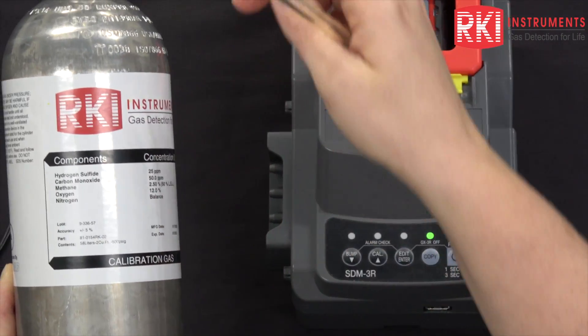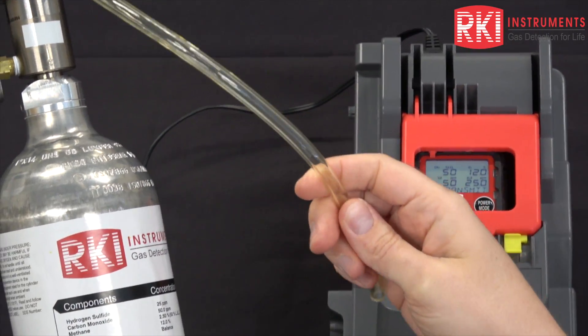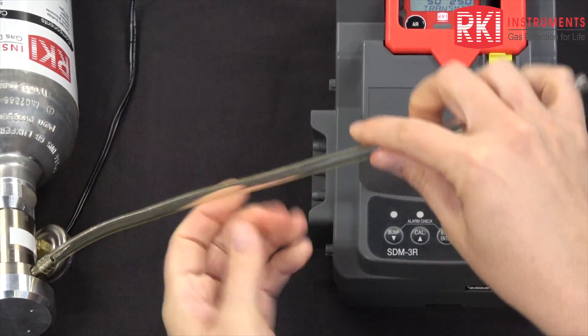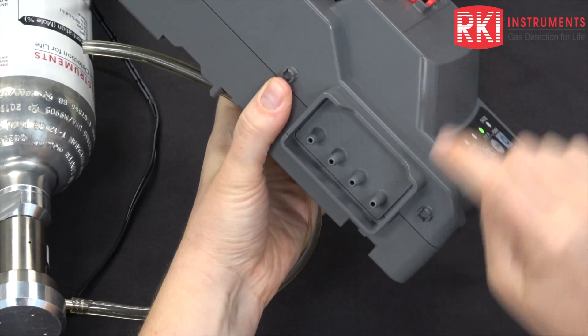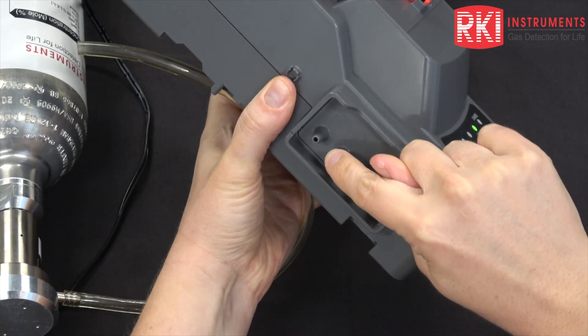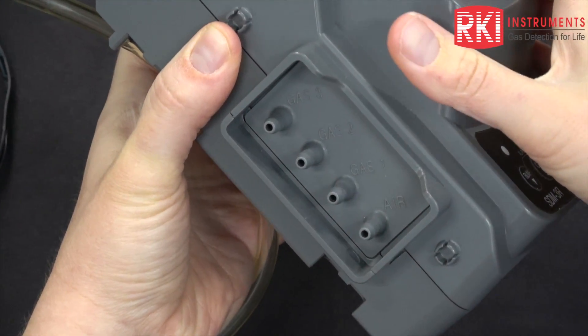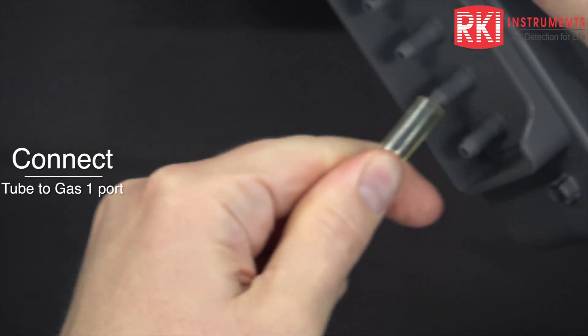I have my calibration cylinder, a demand flow regulator, and my calibration tubing. I'm going to connect my cylinder to the gas 1 fitting on the side of the SDM-3R. The fittings are: air, gas 1, gas 2, and gas 3. Gas 2 and 3 are only used for calibrating or bump testing a GX-3R Pro, so I'm going to connect to gas 1.